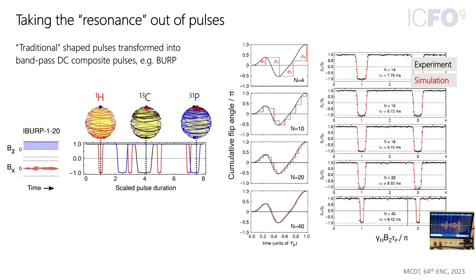A more elaborate example is based on stealing the concept of wideband inversion from Ray Freeman — a BURP pulse. In high field, a BURP pulse is normally a shaped pulse, but they managed to discretize it to make a DC composite pulse. You discretize by making steps in the cumulative flip angle throughout the BURP pulse profile, and discretizing to different resolutions changes the bandwidth. The pulse itself introduces the resonance, so you don't have to rely on hardware for resonance, since getting accurate timing is fairly easy. A pulse can be about 10% off resonance and still have high-fidelity excitation.